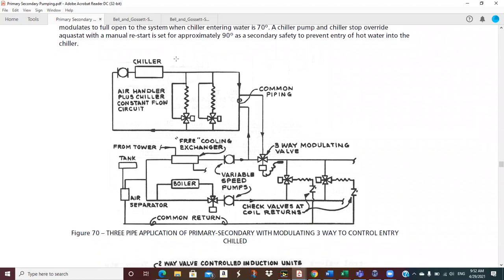I'm not going to talk through this. I'm not aware of anybody that really does three-way pipe stuff anymore. The idea is I've got hot water coils and chill water coils, and I've got two different distribution lines, but I've got one return line. So I'm going to dump the return out of the hot water coil and the return out of the chill water coil together and mix them. And then I'm going to take that and split it and put it back in the boiler and chiller.